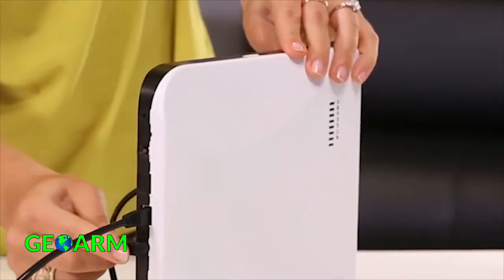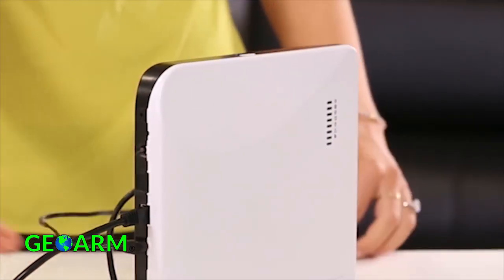The Connect Plus system will emit a long beep and the top five LEDs should turn green, with the top one blinking indicating AC power. It may take up to 30 seconds for the communication LEDs to come solid green.